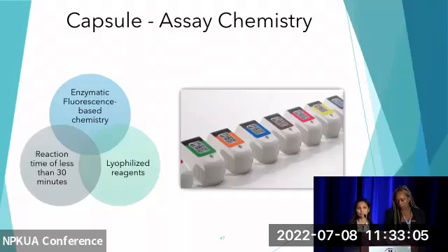Additionally, we have also introduced some freeze-dried reagents in our capsule, which means that we have some reagents in the form of beads. This helps us a lot because it increases the shelf life of the capsule, so you can have a longer expiry date, but also you can store the capsules at room temperature instead of having to store them in your freezer. So it actually gets rid of the entire cold chain.